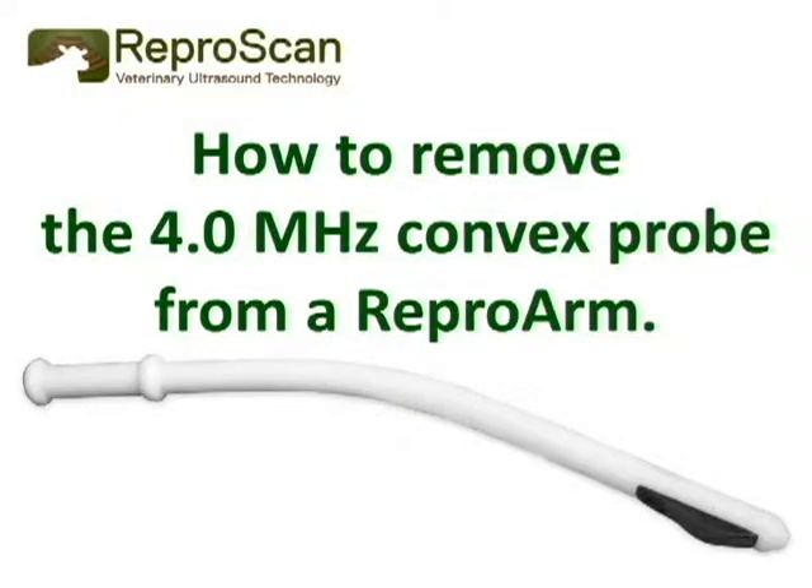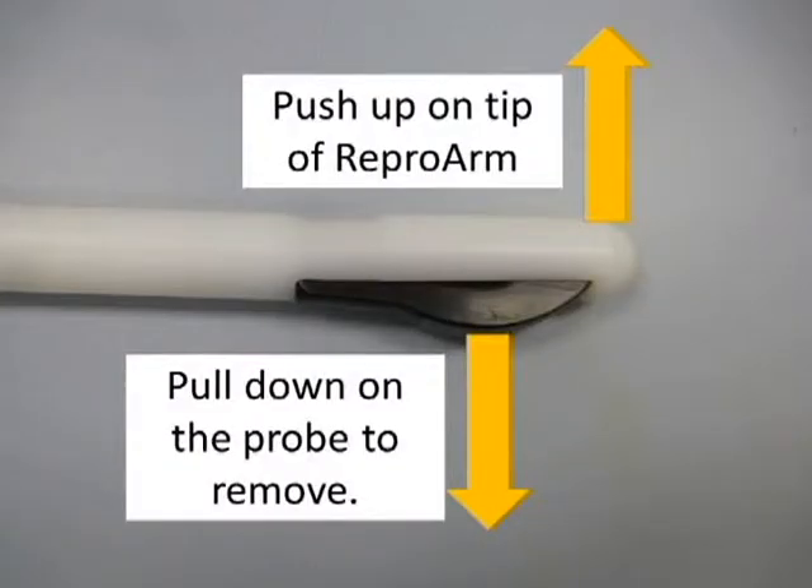Now let's look at how to remove the 4.0 convex rectal probe from a repro arm. Push up on the repro arm and pull down on the probe to remove. Push up on the tip of the repro arm and pull down on the probe at the same time.